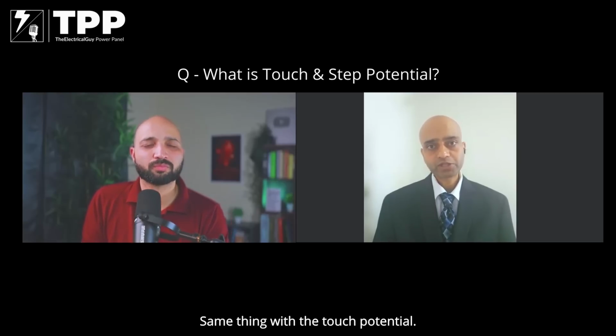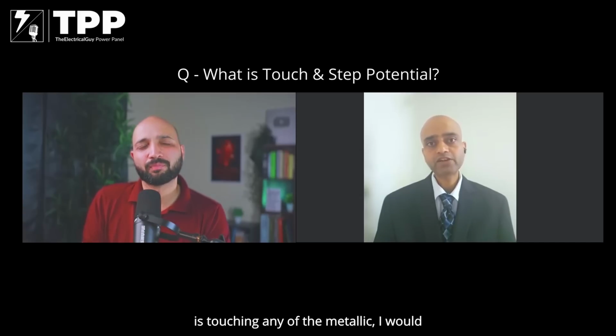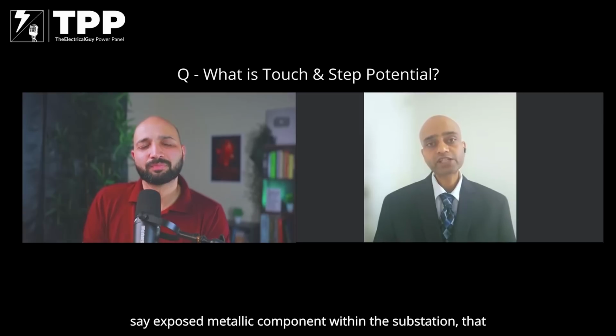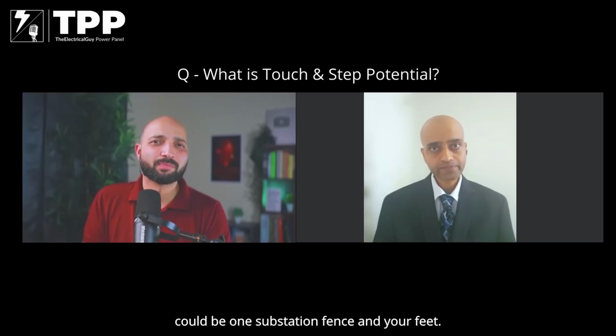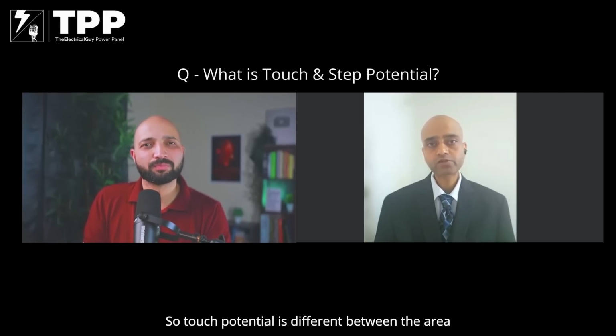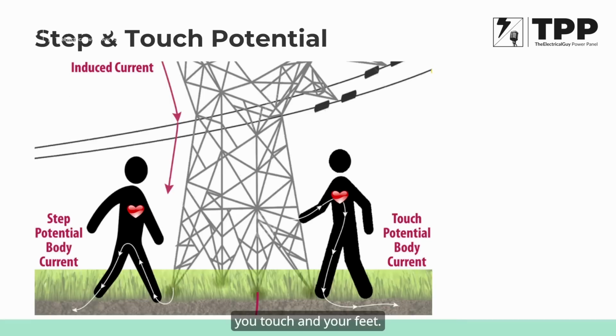Same thing with touch potential. When your hand is touching any exposed metallic component within the substation, that could be the substation fence, and your feet—that's the difference. Touch potential is the difference between the area you touch and your feet, while step potential is the difference between your two feet, which is roughly one meter apart.